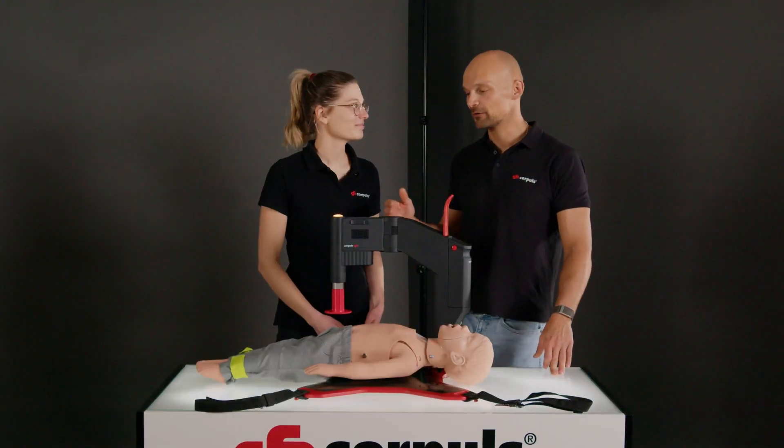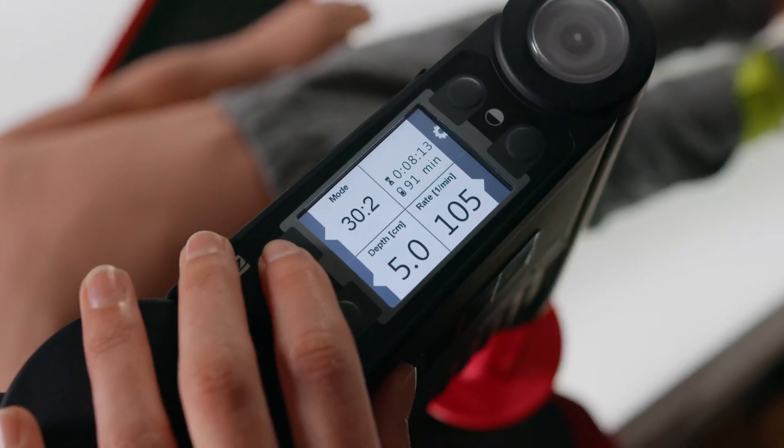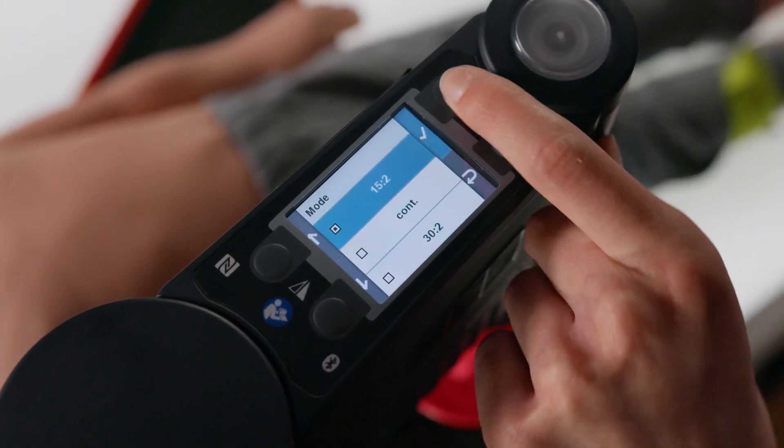Would you like to briefly run through how to change the settings on the Corpuls CPR for children's resuscitation? Sure. Firstly, I'll change the mode from 30:2 to 15:2. Now I'll adjust the pressure depth in accordance with the current guidelines, which corresponds to one-third of the chest height. For a child with a chest height of 14 centimetres, this is 4.7 centimetres.